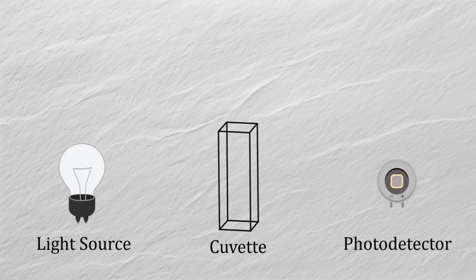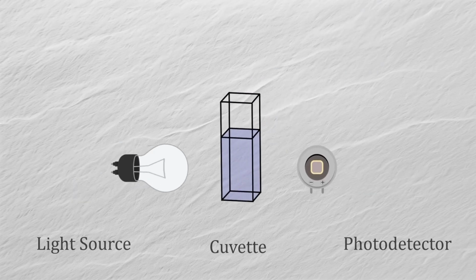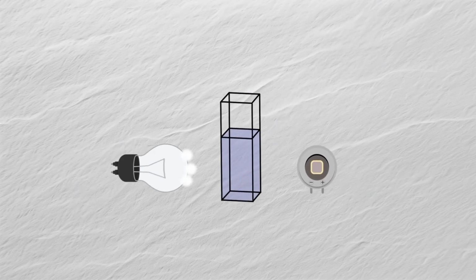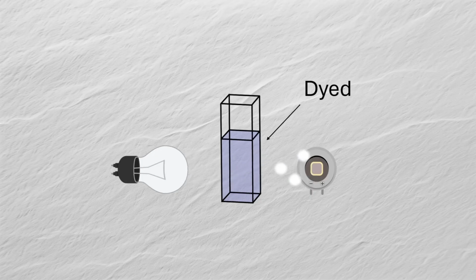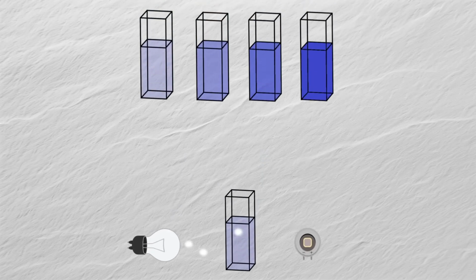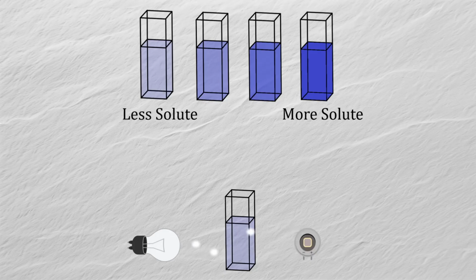In its simplest form, the light at a desired wavelength or color is shown through the cuvette holding the sample. The sample itself has been chemically dyed depending on what solute is being measured. The intensity of the dye is proportional to the concentration of the solute. So more solute means you'll have a darker color. Less solute means lighter color. This will affect the amount of light that's absorbed by the solution and transmitted to the photodetector.